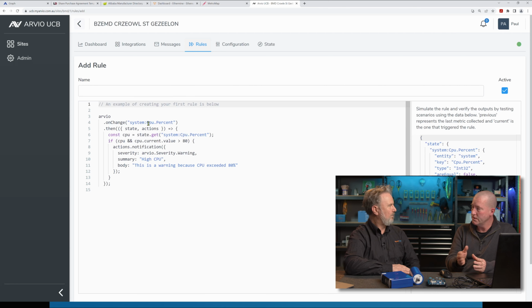It can be on the Ethernet on the LAN, or it can be on USB. On the LAN you're doing Modbus TCP, so you'd need to know the IP address of the device and port number, and you can reserve that in the router. If you've got a dynamically assigned device that always gets its IP from the router, you can go into the router and say, if you see this MAC address again, always give it .15 - a fixed IP. Once you've done that, it's really got a fixed IP.